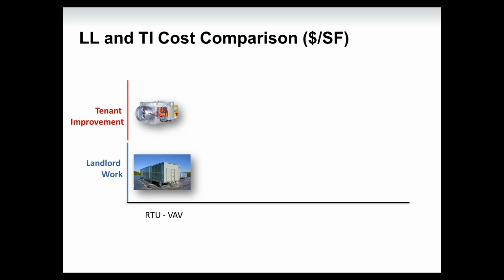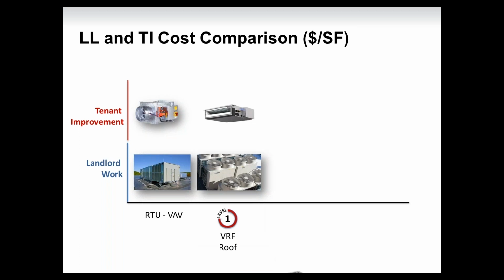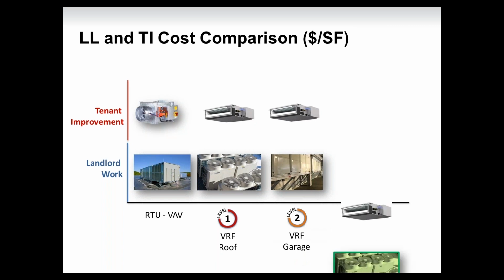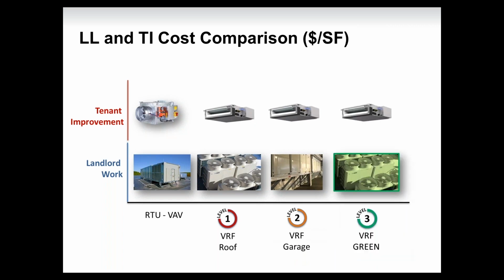So let's compare what HVAC components will be in the landlord's and tenant scope of work for this analysis. For the base design, landlord work will include the rooftops, the duct loops on each floor, as shown on the following slides, as well as the VAV boxes for control of the entry corridor on the first floor and the restroom core work. For the VRF options, the outdoor units, whether we locate them on the roof or in the parking garage, are included. So we are going to provide 3 options for VRF design for this building. The first option is to put VRF equipment on the roof. The second option is to put VRF equipment in the garage. And the third is to offer a VRF green building solution.